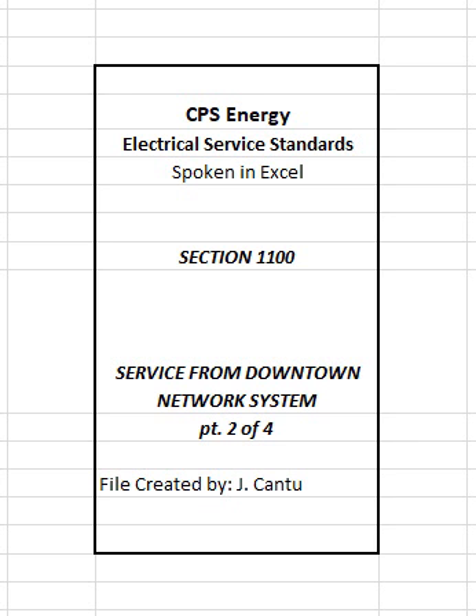In addition, the design shall meet accessibility requirements listed below. 1. Maintain a clear access route for delivery and installation of CPS Energy equipment. 2. There shall be a 73-inch x 97-inch slab at an outside entrance, ground level, to receive transformers weighing up to 20,000 pounds each. 3. Entrance is to be readily accessible and not be blocked vertically 50 feet or horizontally 12 feet in front and both sides of slab opening for crane operations, no exceptions.